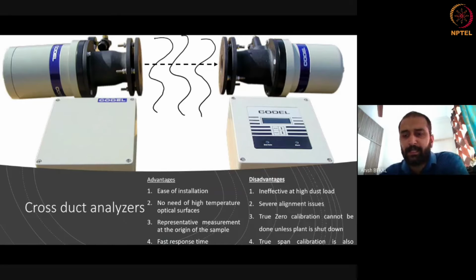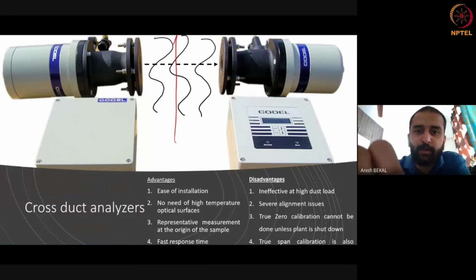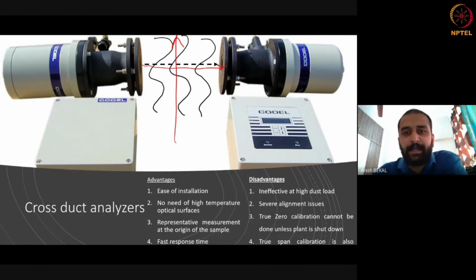Okay, so let me go across all these three types of analyzers that exist and tell you which is good. This, for example, is a cross duct analyzer. What happens is the gas flows like this, and the light moves from the transmitter to the receiver, and in this process it is passing through the gas, and you are measuring the properties of the gas. It is relatively easy to install, even though the temperature of the gas can be anything, and it's now separated by a window, so you don't need high temperature optical surfaces. And since you are measuring the sample at the place where the sample is being propagated, it's a very, very good representative of the sample that comes.